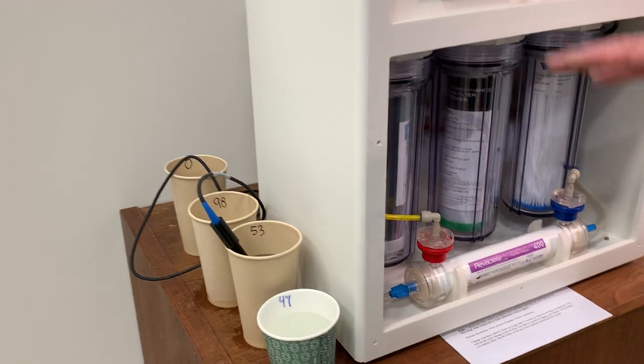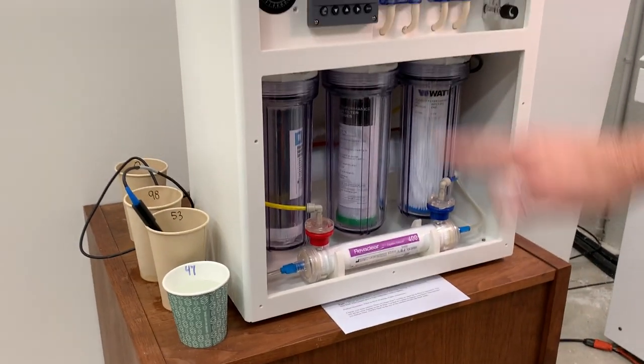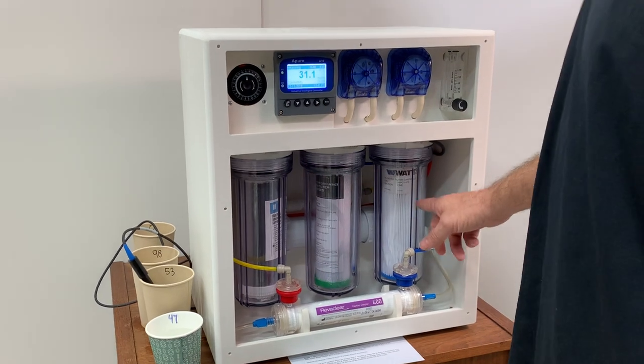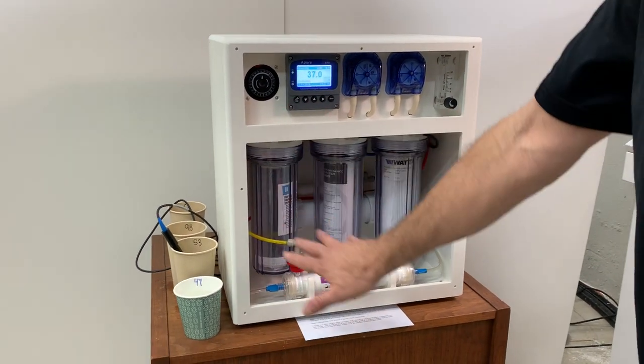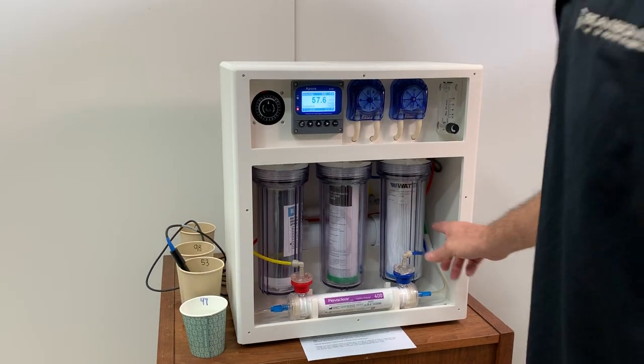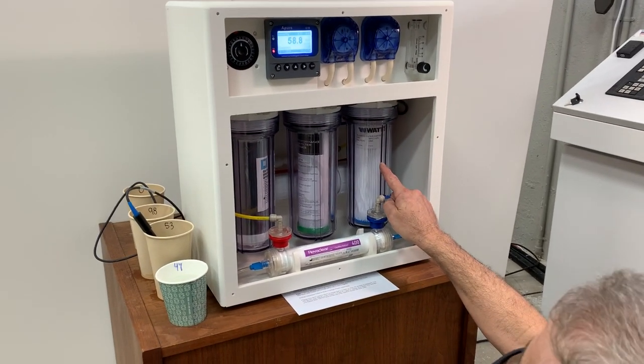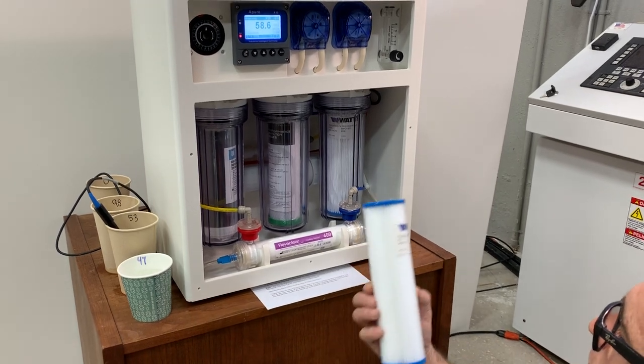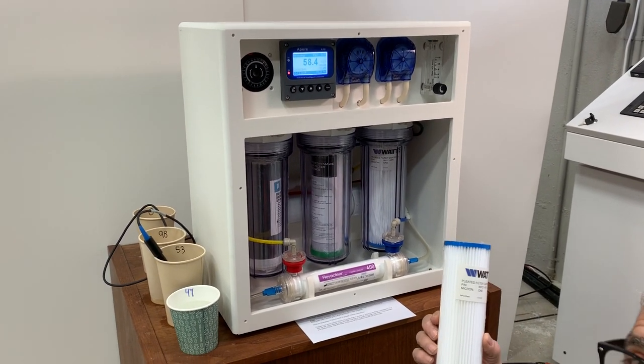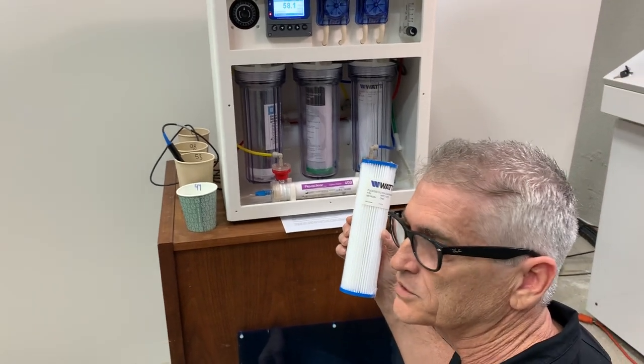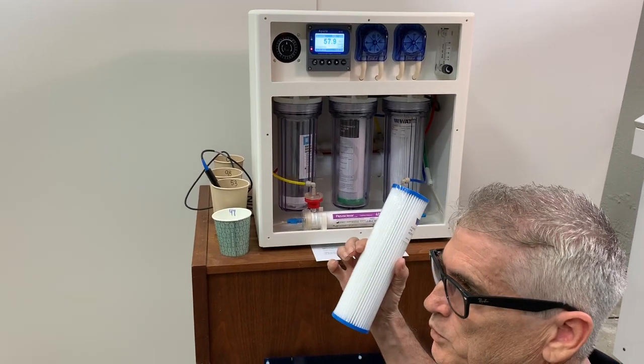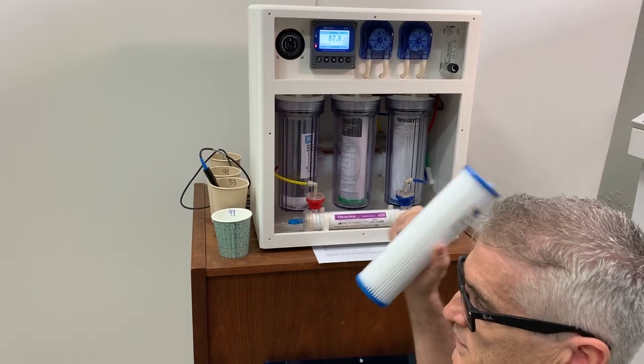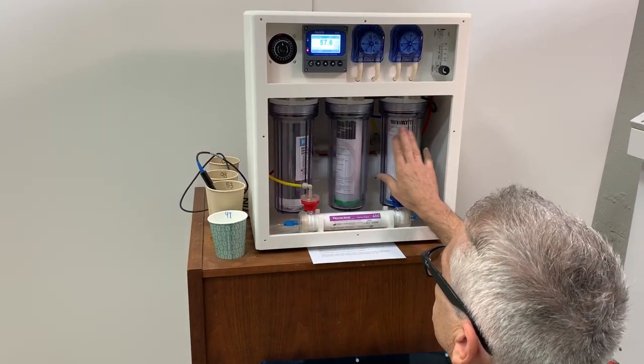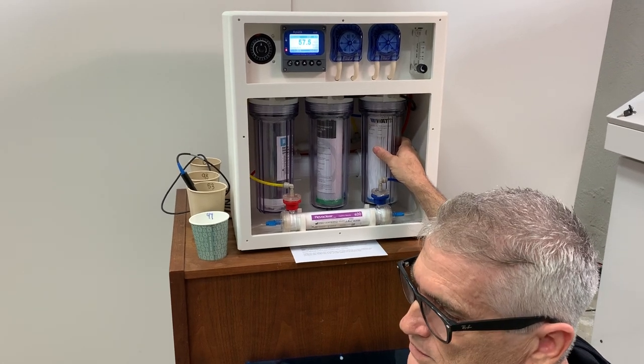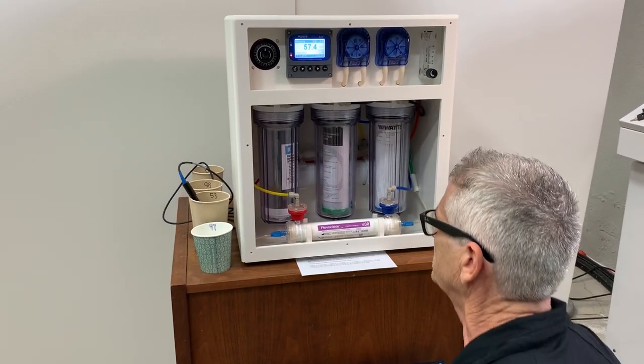So let's for now go over a little bit of the basics of the machine first before we move into the controller. It's the same design below as the previous dialysis machine. We do have a 1 micron pleated filter, which is the first filter in line from your house water supply. So this is a very fine filter. It will take out all the iron and particles down to 1 micron. And since these canisters are clear, you can pretty easily see when they need to be changed.